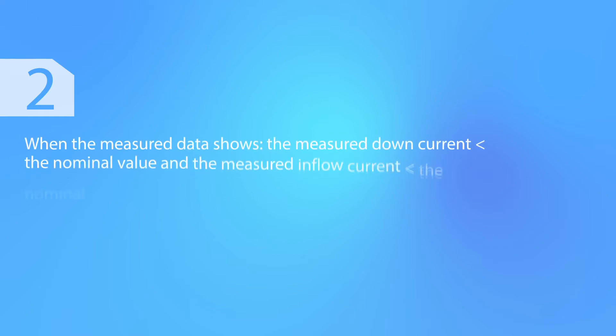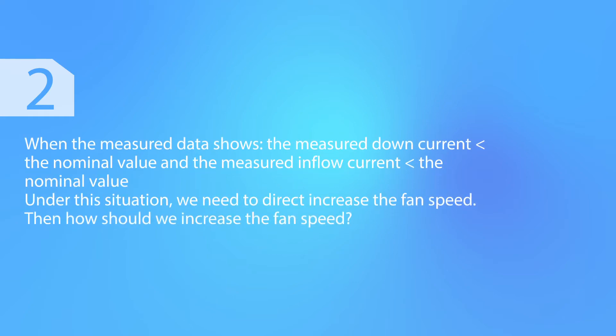When the measured data shows that the measured down current is below the nominal value and the measured inflow current is also below the nominal value, we need to directly increase the fan speed. How should we increase the fan speed?